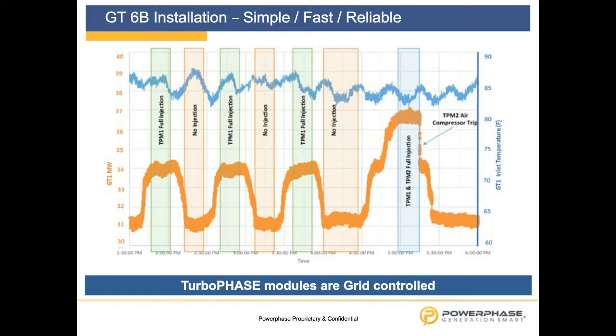You see here on the orange side the base load of the gas turbine, which is 31 megawatt, and then you see 3 cycles. These are real-time performance test data, in which the first 3 cycles are the injection from 1 Turbophase module, and on the right side the last peak is the 2 TPMs injected into 1 gas turbine. Then we initiated a trip on the right side, and the gas turbine went back to base load. So as I said, real-time data.